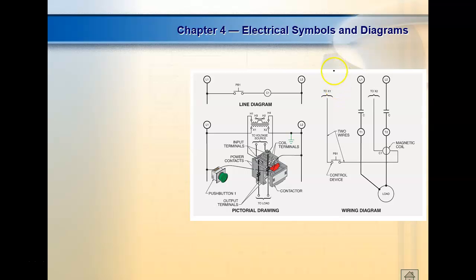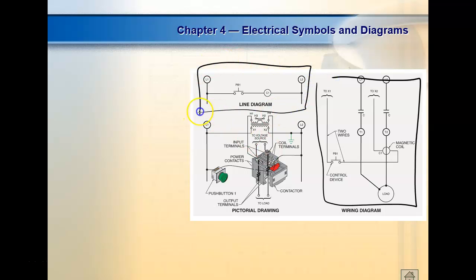So this is a wiring diagram, and this right here is a ladder diagram. On a line diagram, a lot of them put the control circuit within the line diagram, and those get pretty complicated. You'll see this a lot on HVAC systems, but hopefully they put the ladder diagram up there, because it's drawn the way the circuit logically operates, so it's easy to figure out. With a wiring diagram, when they put the control circuit within the line diagram, all I know is this relay is set to control this line right here—that's all I know, but they draw it across the line.